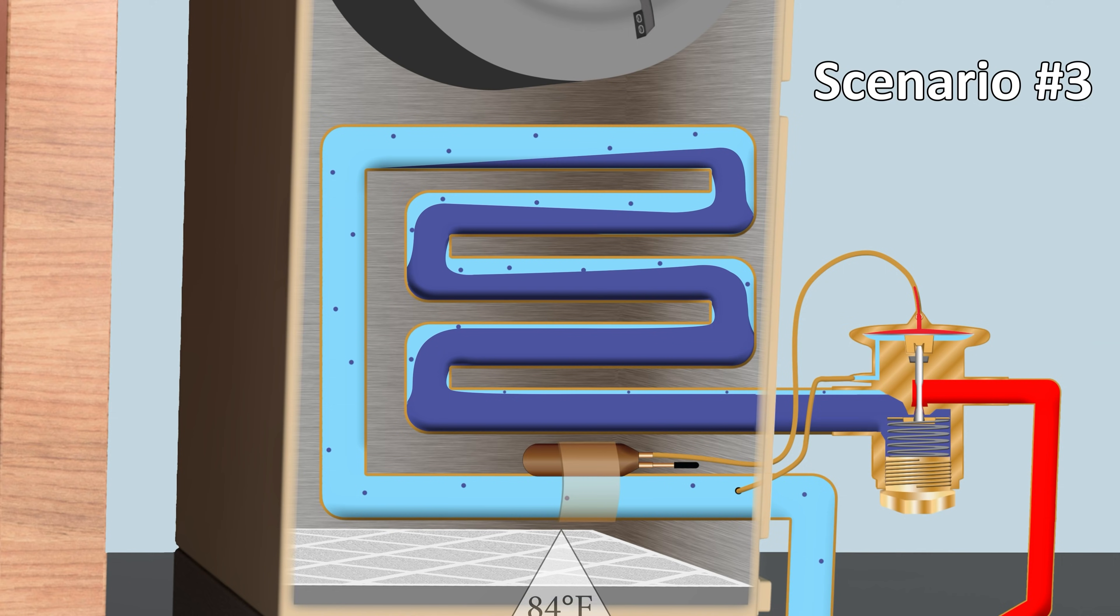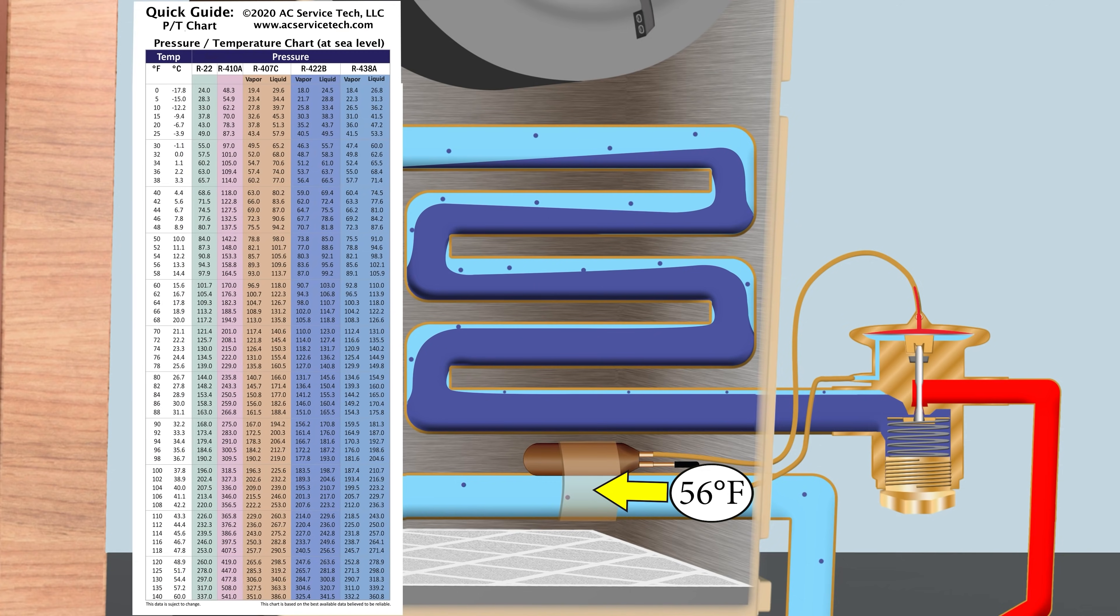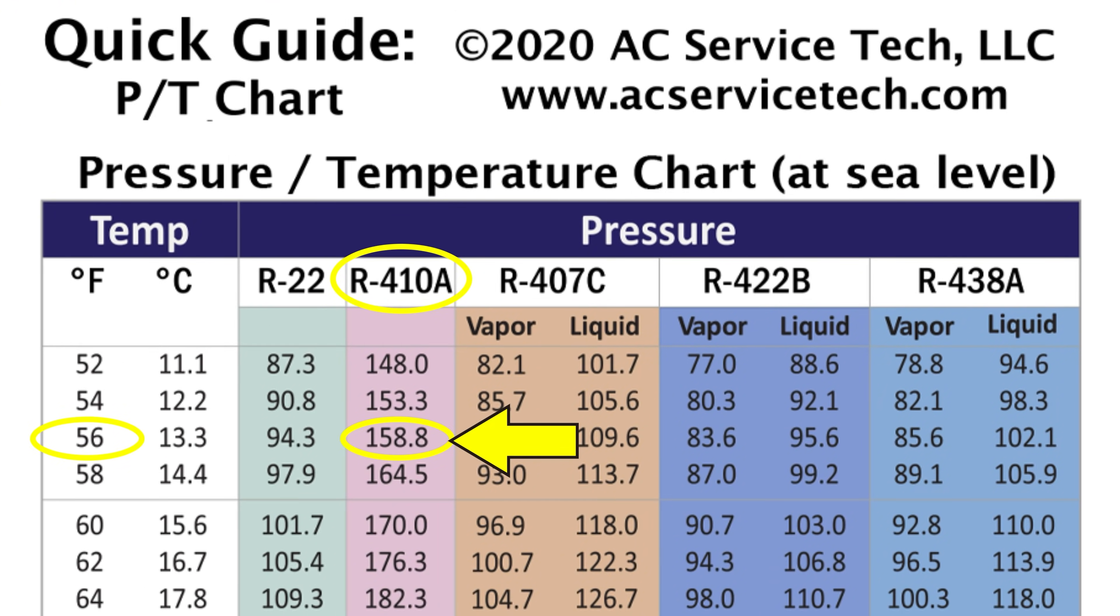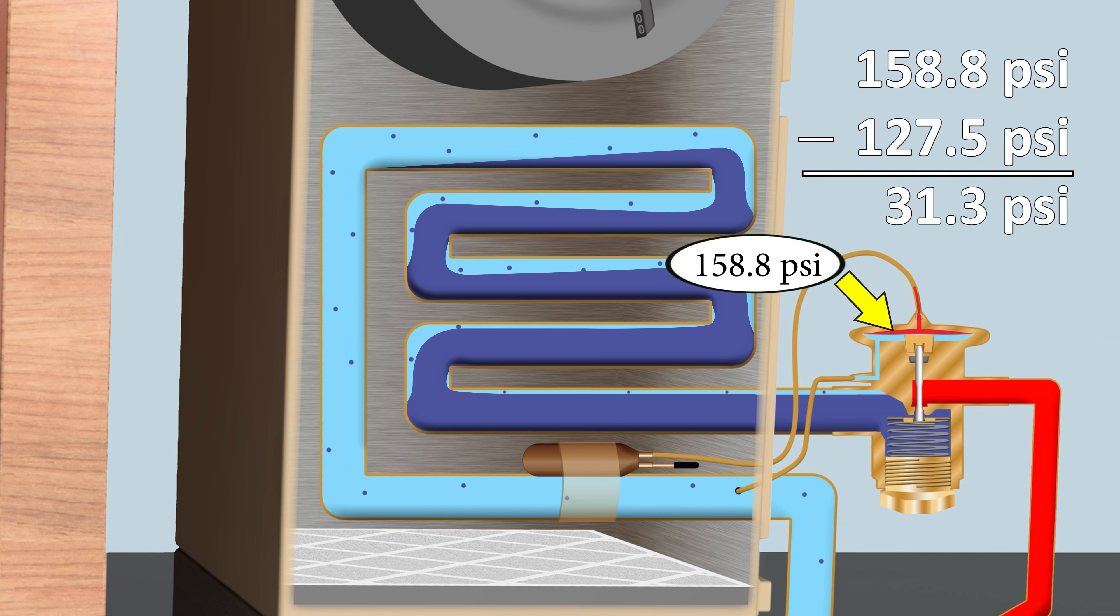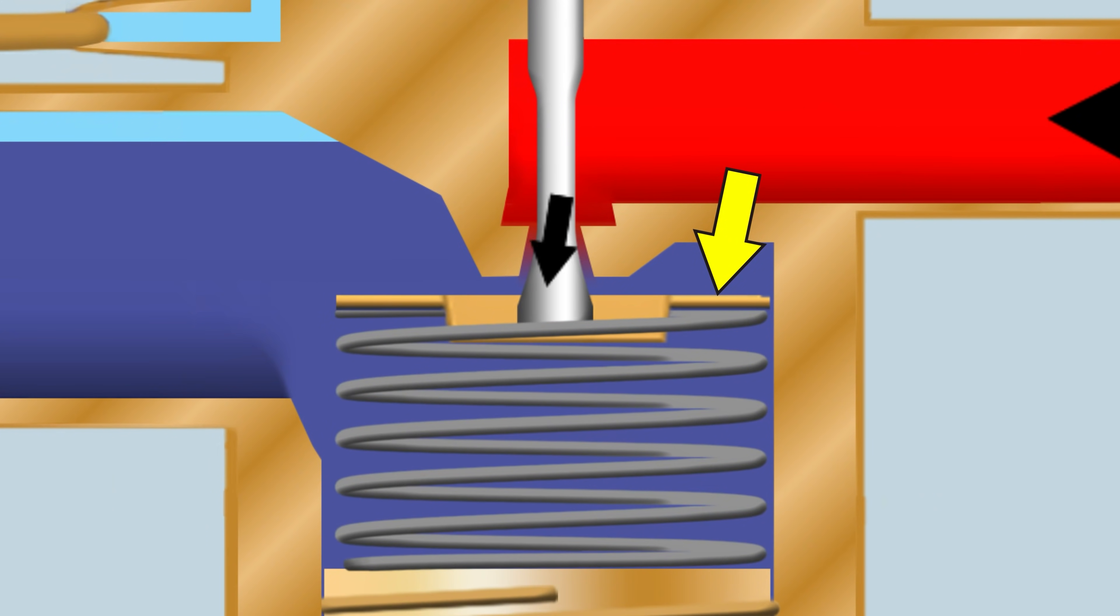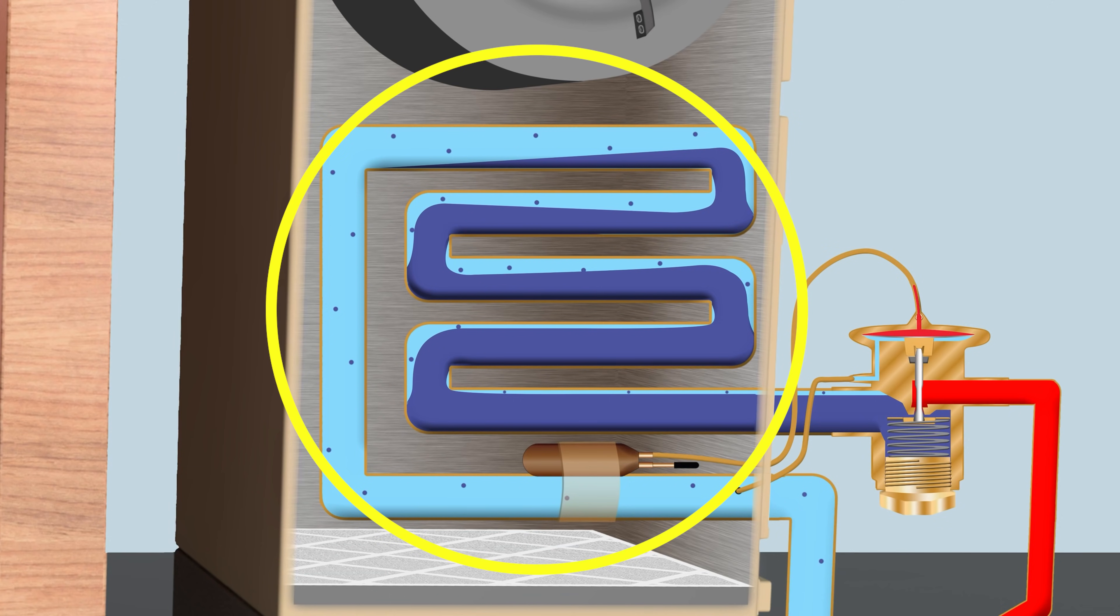For scenario three, we have the system being turned on for the first time, and it's say 84 degrees in the building, high humidity, so you have a high heat load. In this case, we have a vapor temperature on the bulb of 56 degrees. If we convert that to a saturated pressure for R410A, we have 158.8 psi, and we have a vapor pressure on the external equalization line of 127.5. So we take 158.8 minus 127.5, and we're left with a spring pressure of 31.3 psi. Now in this scenario, you can see that our spring is compressed even more. Our opening size is even larger, so we have to allow more refrigerant into this coil, and we still have a superheat of 12 degrees.